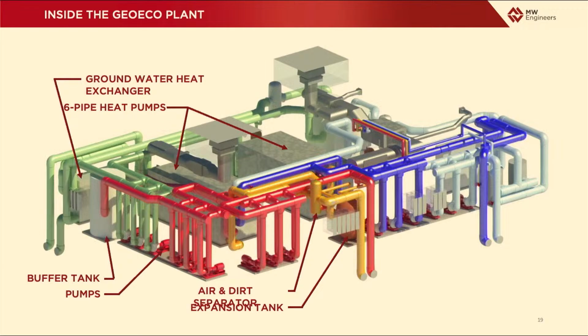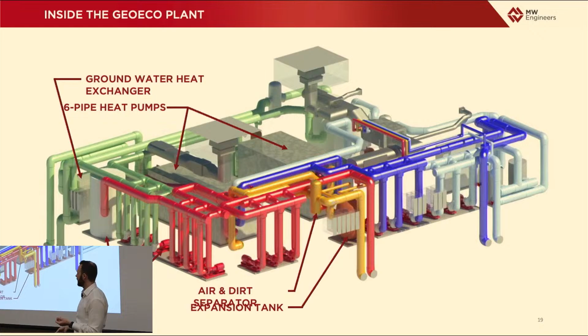These pumps, the pumps are what actually move the fluid. So it moves the fluid around campus to all the buildings, back to the GeoEco plant, and then through all of this equipment. And you can see the pumps around the perimeter. The air dirt separator is what's suspended in the air, and that's pulling dirt out of the water. Dirt can clog things, and it's pulling air out of the system. Air can be really damaging to water systems. The expansion tank, you can kind of read it down there, is the tank here. And what that's doing is as you heat up and cool down water, it expands and it contracts. And there has to be somewhere for that expansion contraction to go, or you can pop pipes and blow holes in things. Not really good. So this is a tank that's filled with air and has a medium that separates the water from the air to allow somewhere for that to expand.